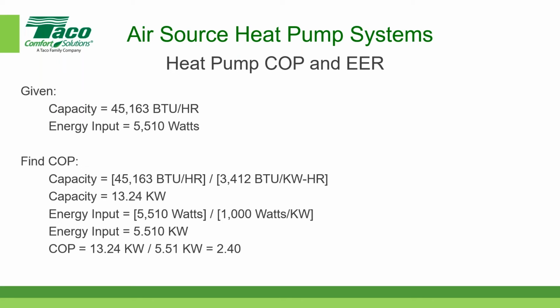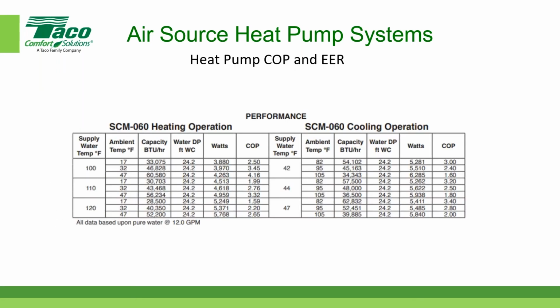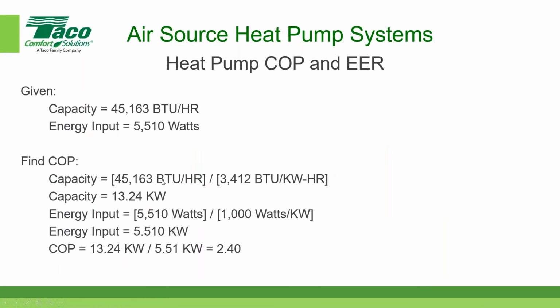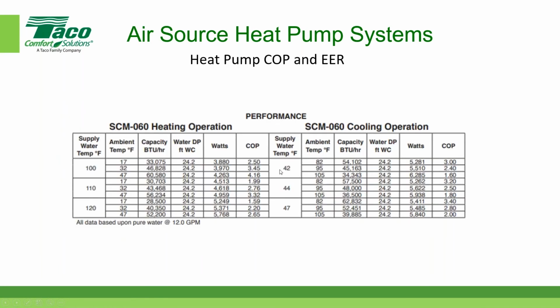No. Okay, so you can look on a table. I took this information from a table, and I just did the arithmetic, and it came from this table right here. So let's look for that capacity in terms of the heating capacity. The cooling capacity was 45,163. So over here on the right-hand side, in order to supply 42°F water at a given ambient air temperature, the air outside, I am going to have a capacity of 45,163. And there's the watts, 5,510 watts. And if you use that formula that I just did, you'll come up with the same COP that's in this chart.